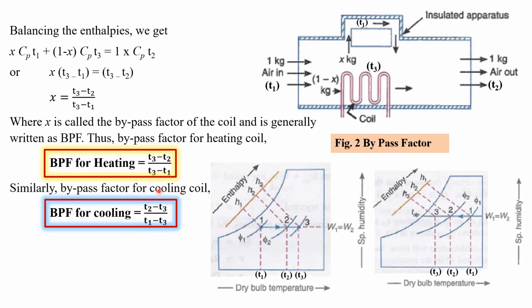So for this case of heating, it is defined as T3 minus T2, that is the difference of temperature at the exit, divided by the difference of temperature at the inlet. So it's (T3 minus T2) divided by (T3 minus T1). Whereas for the case of cooling, it's slightly different. Now the air is made to flow over the cooling coil at temperature T1. The cooling coil is maintained at temperature T3, whereas the actual exit of the air from the system is now at T2. So for the cooling process, the subscripts are interchanged. Now it is (T2 minus T3) divided by (T1 minus T3). So we observe that in the case of sensible heating, the temperature of air exiting the system is lesser than the temperature of the heating coil, whereas in the case of sensible cooling, the temperature of air exiting the system is greater than the temperature of the cooling coil.